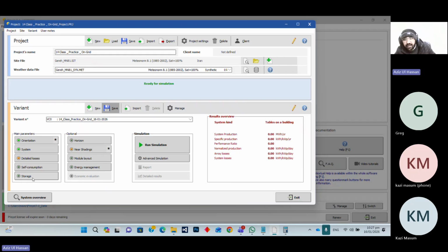This BESS is basically used for three purposes. One is peak shaving, one is self consumption, and the third one is grid stabilization. Most of the time our grids are not stabilized, and we have to put that BESS to stabilize it. And also self consumption, if you have any self consumption on the grid, you can use that. And the third one is peak shaving. You will cut off some energy from the solar and save the energy in the battery systems and use it at the time of the peak hours.